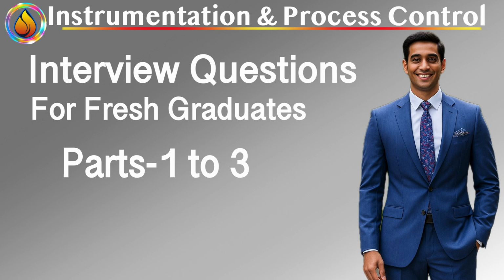What is 3-element control in boiler drum level systems? It uses 3 inputs, drum level, steam flow, and feed water flow, to stabilize level during load changes. This compensates for shrink and swell effects, ensuring safe, steady boiler operation.